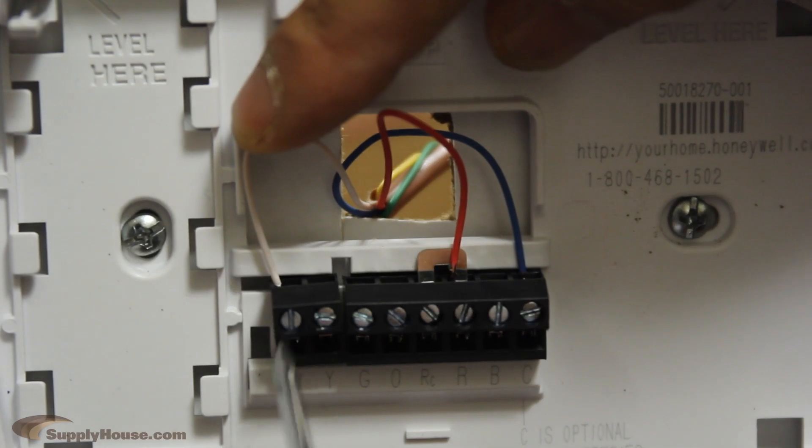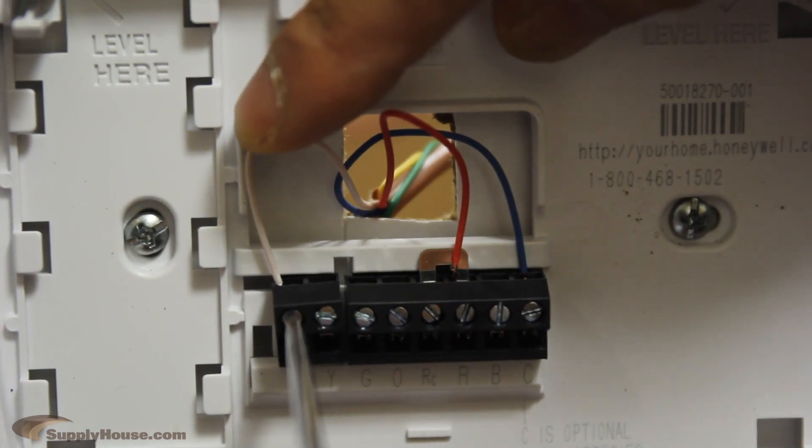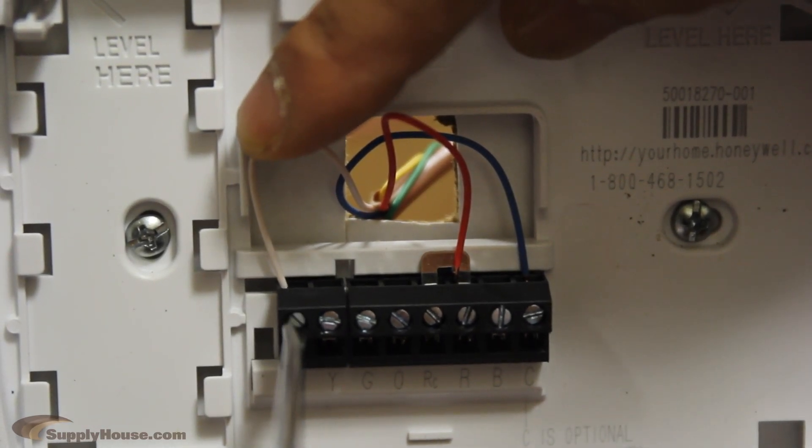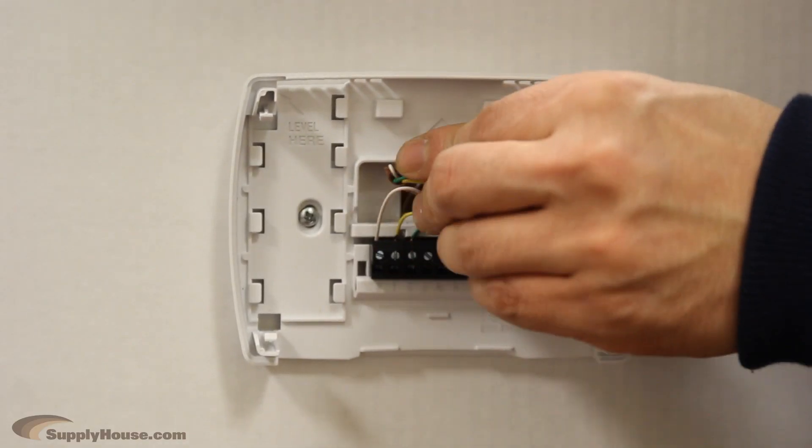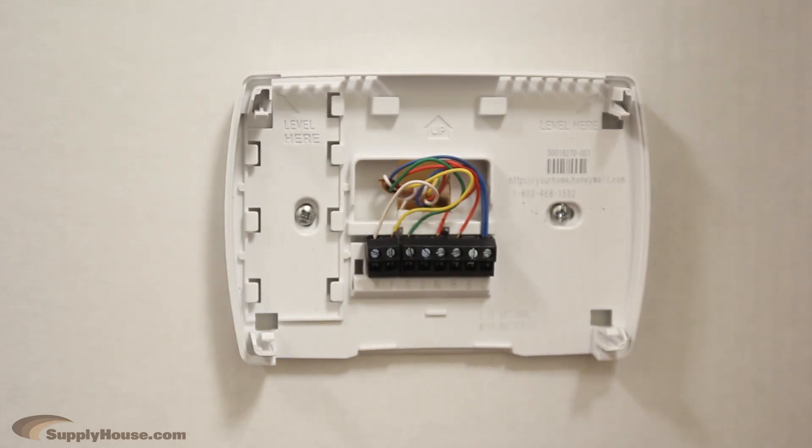The W is the call for heat and is wired to the W for the furnace, heater, heat zoning panel, or actuator valve depending on your system. Then, push the wires back into the wall and attach the thermostat to the plate.